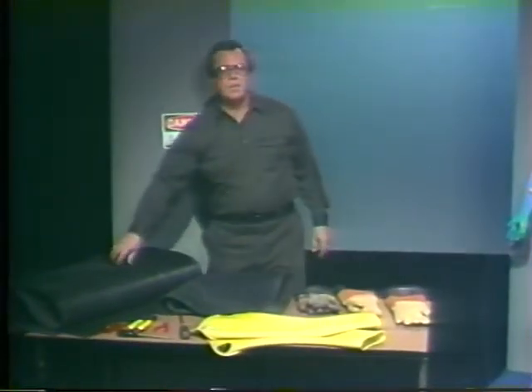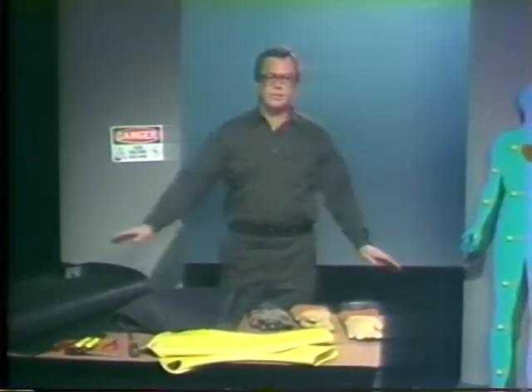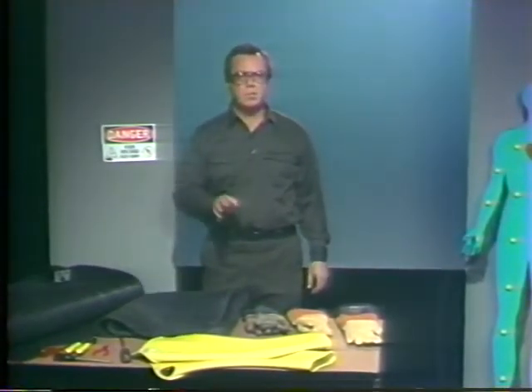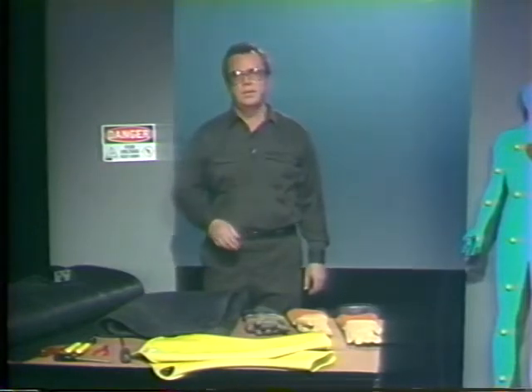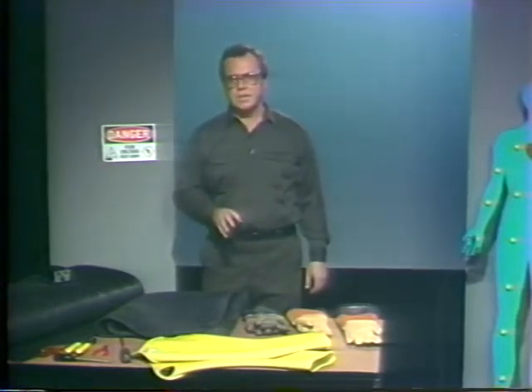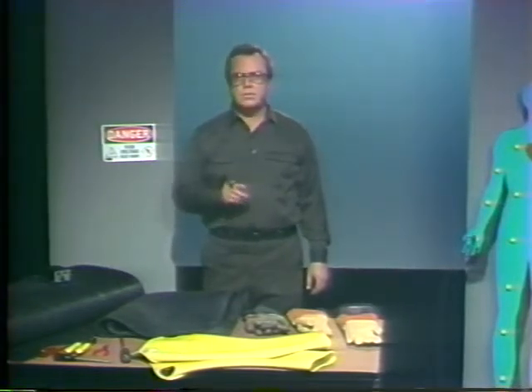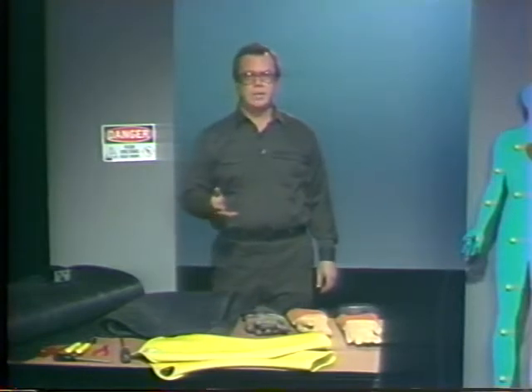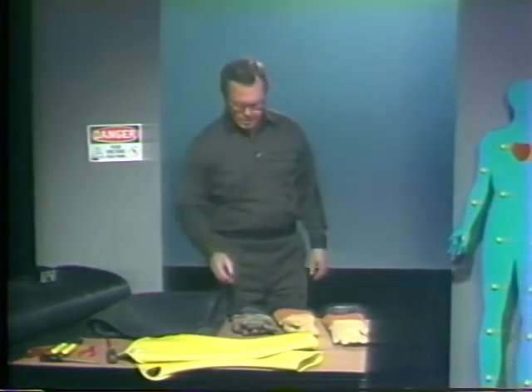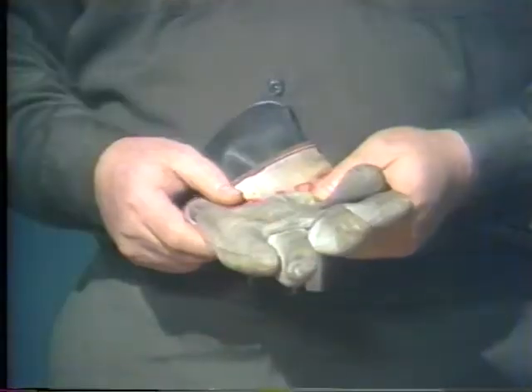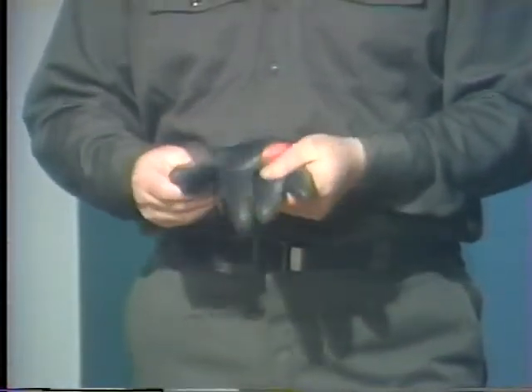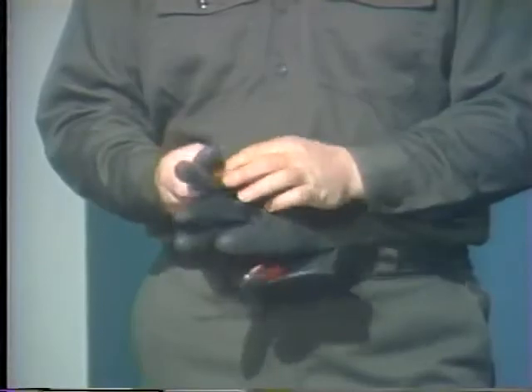Now, all of the protective equipment we've been talking about is insulation. Gloves, sleeves, blankets, and floor mats insulate you from current sources or from ground. So before you use any of this gear, you have to make sure that the insulation is in good condition. Before you start a job, there are a few simple checks you can make. It's a good idea to inspect your gloves before each use. Check the rubber. Look for cracks, worn spots, cuts, and holes.